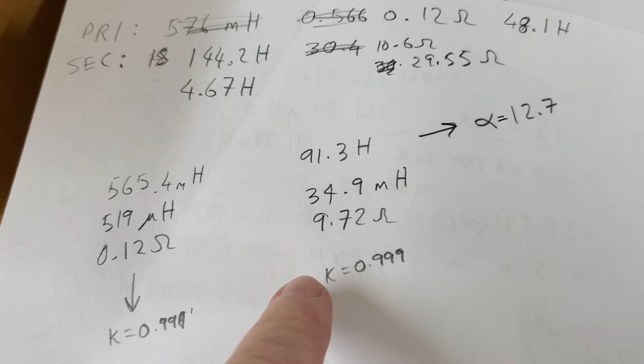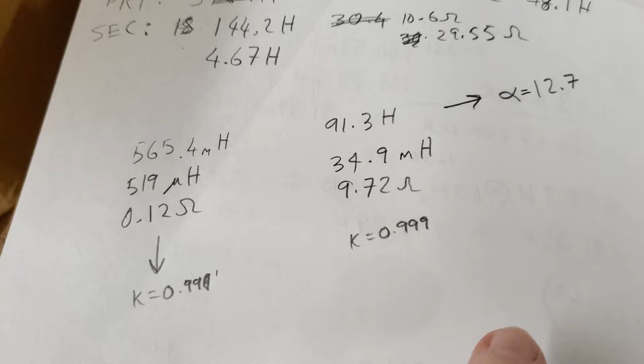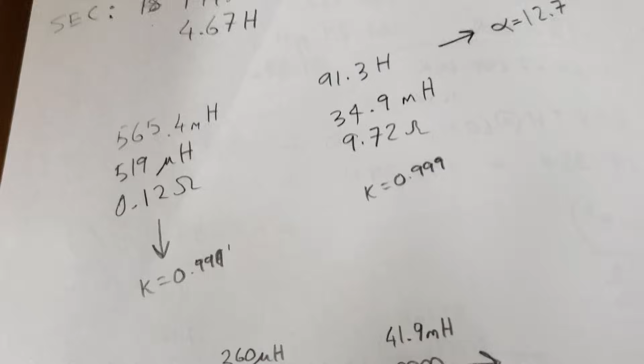You look from the secondary, you see 91.3 henries. You short the primary, you see 34.9 millihenries. It's 9.72 ohms. That also gives you a coupling coefficient of 0.9995 and a little bit, so pretty darn close to perfect. The turns ratio, if you divide these inductances and take the square root, is 12.7, which is kind of an unusual transformer. So if this was 120 volt, it'd be like 120 volt to like 1524 volts or something like that. Not entirely sure what this transformer was for.